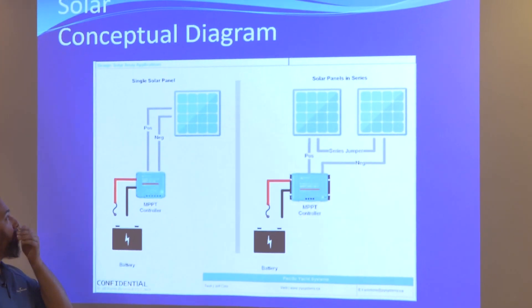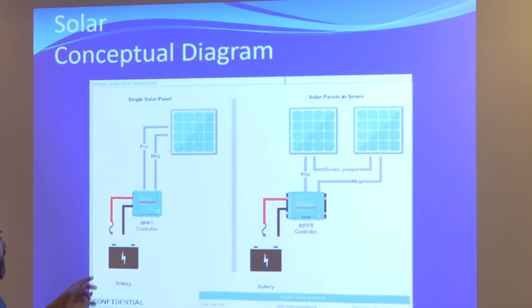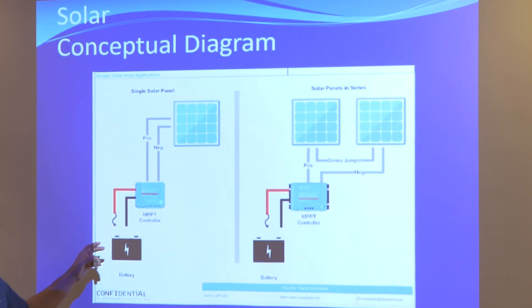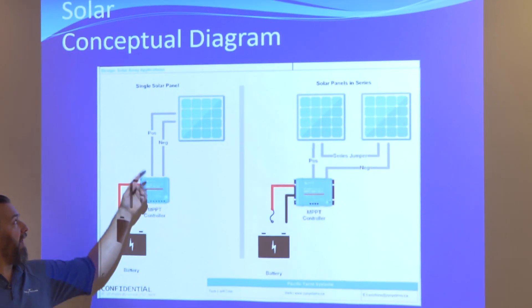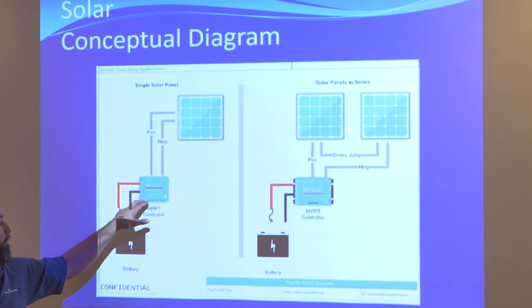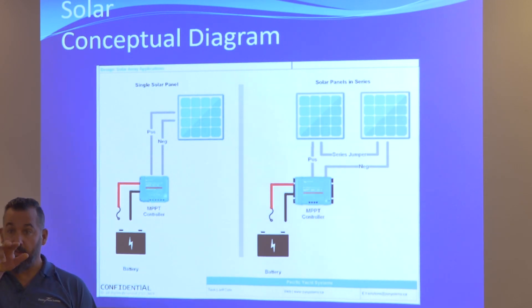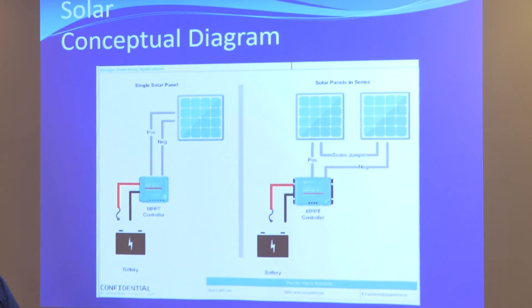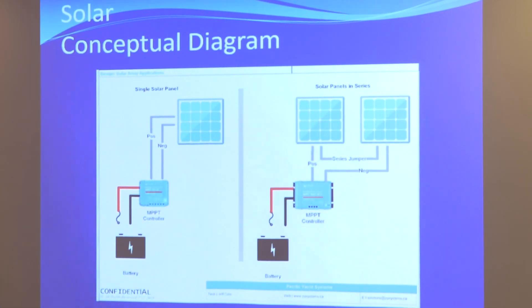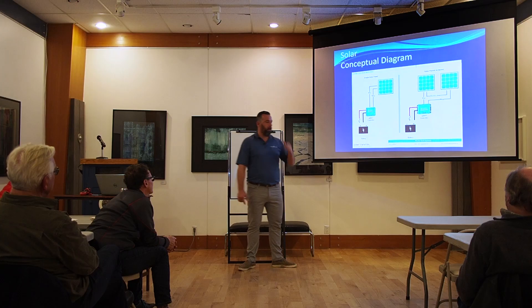What you're going to want to measure, two things. First of all, you make sure the fuse is still there. How can you tell? You go to the controller, you have a blanket on top of the solar panel, and you actually measure on the battery posts. They're generally exposed, they're set screws. You can actually get your little multimeter there. And you want to make sure that you see battery voltage at the controller. That's the first thing. You want to confirm, hey, do I have connectivity to my battery? Yes. Check. Great.